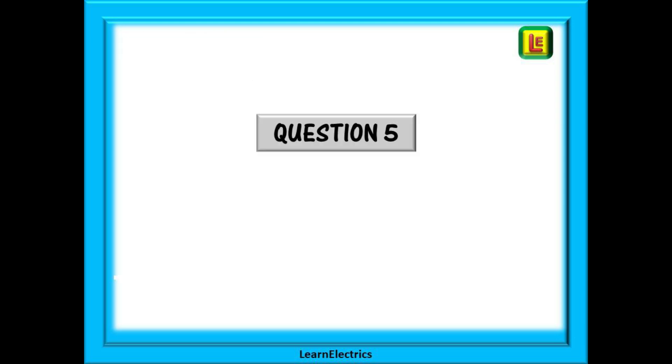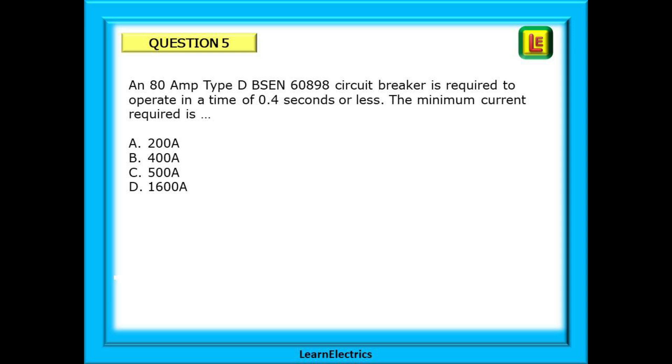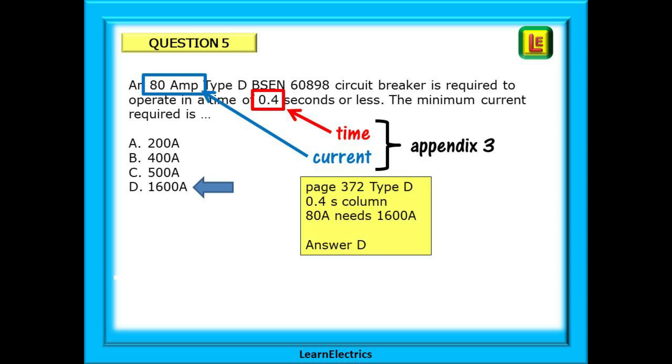Question 5 next. An 80-amp type D BS EN 60898 circuit breaker is required to operate in a time of 0.4 seconds or less. The minimum current required is... And you will need to go to Appendix 3 to find the answer to this question. Pause the video and find the answer. This question talks about time and current, so we need Appendix 3, the time and current characteristics. Find the 0.4 second column, find 80 amps and we have our answer, 1600 amps and answer D.